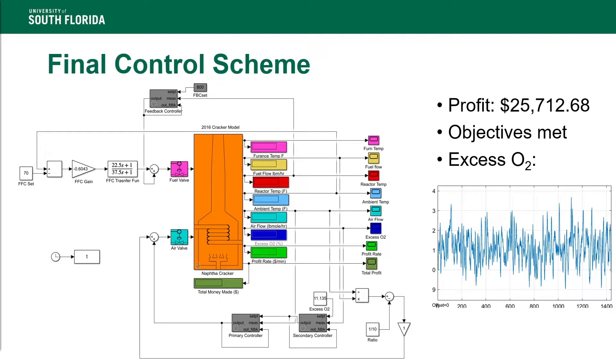After evaluating both alternatives, Alternative 1 showed better control of the excess O2. Alternative 1 was combined with a ratio control, where the ratio controller adjusted the position of the air valve based on the fuel flow to the air flow, which had a ratio of 1 over 10.